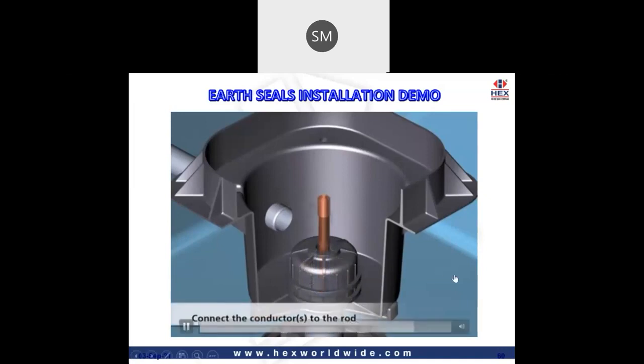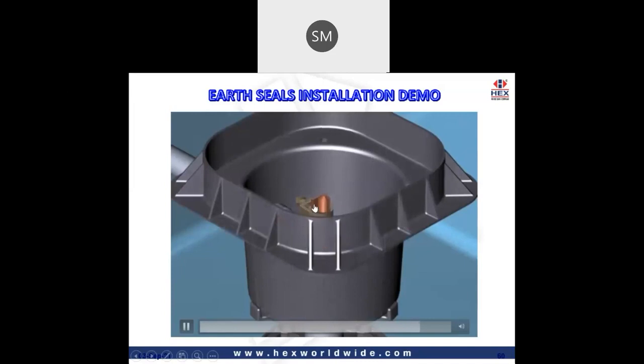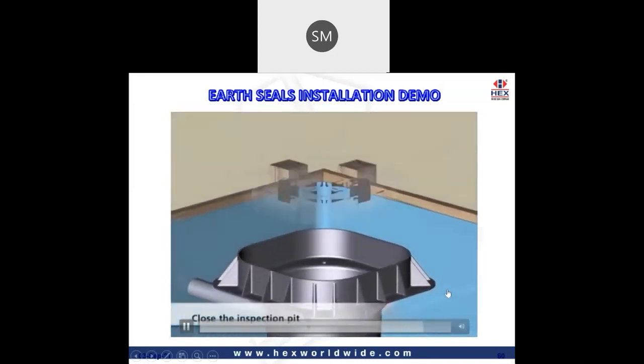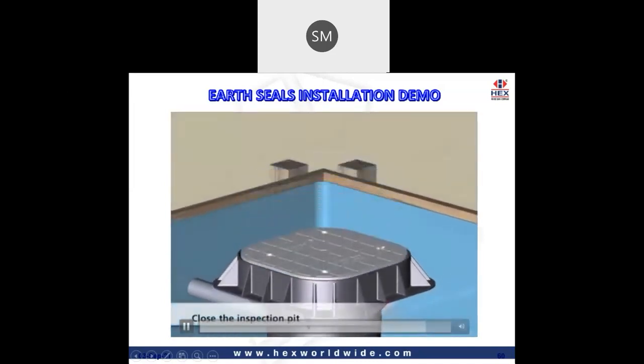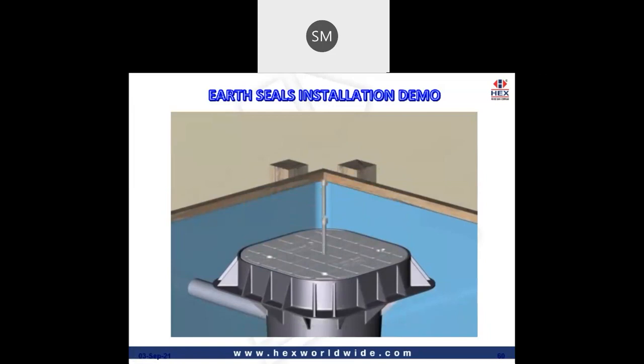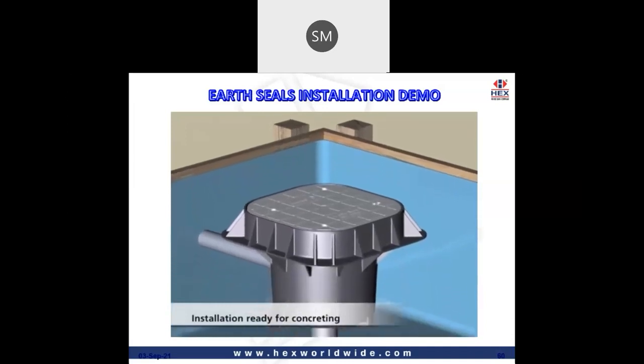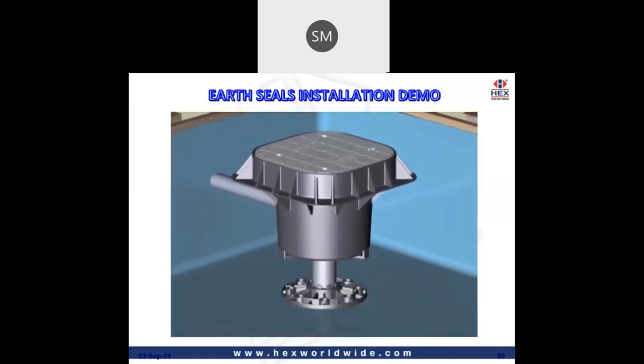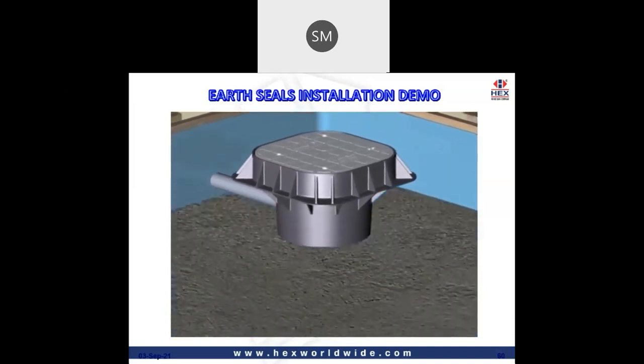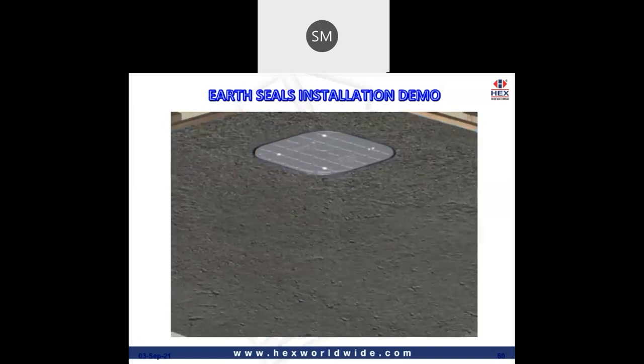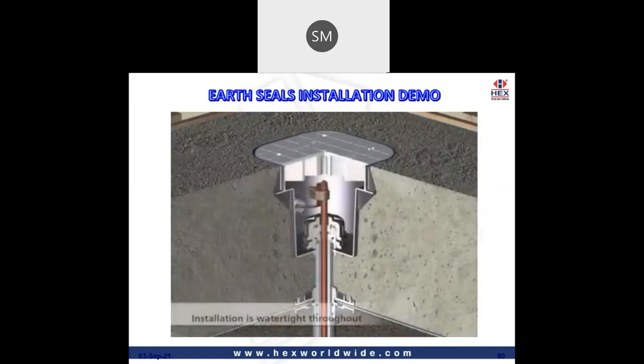After this, we connect the conductor, the strip, to the earth rod, and then we close the inspection pit. It could be a different type of chamber with a hinge lid or whatever we have with us. Once it is kept in proper level with the top of the ground, the top of the basement, we pour in the concrete and the earth pit chamber is in place in a watertight installation.